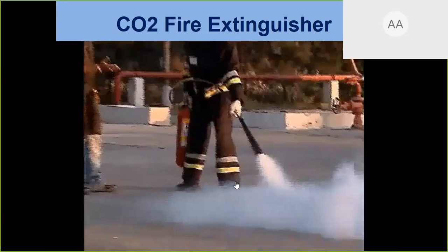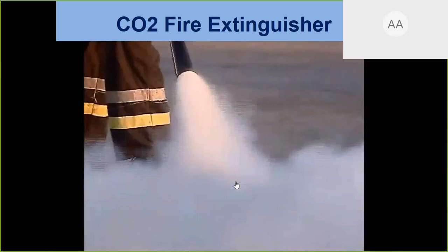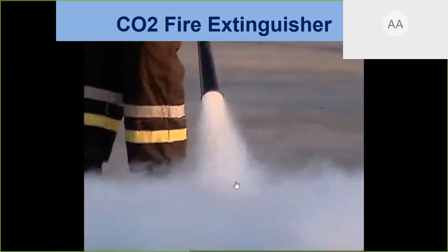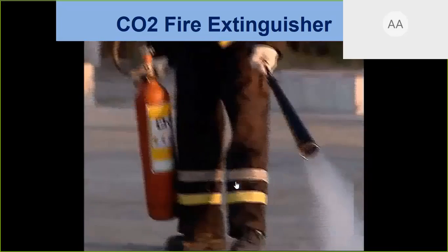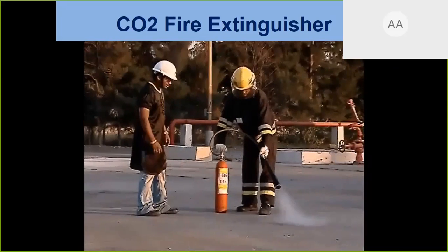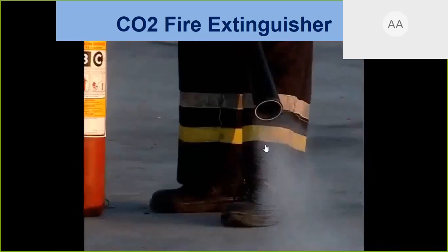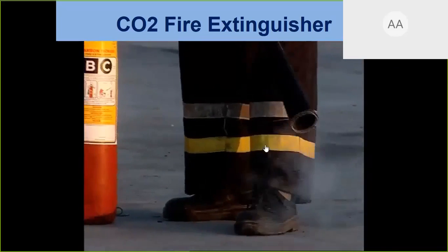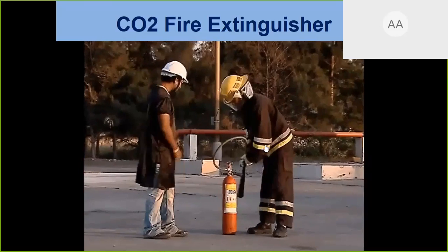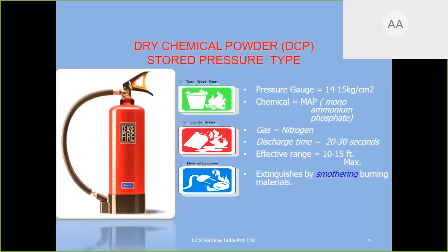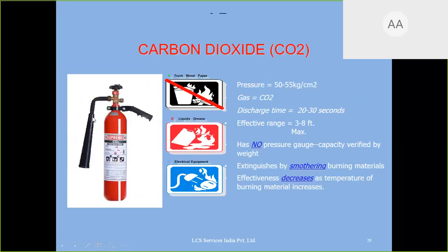So you see how the valve is opened. CO2 is coming out. Right? It is very, very highly pressurized and very cold in nature. So you have to hold it from the handle only. You cannot hold anywhere else. So my dear friends, you must notice that in DCP there is a pressure gauge, right? In CO2 no pressure gauge, and this hose is of the same diameter throughout, right? If I have to find out whether this extinguisher is CO2 or DCP, one is the hose diameter and the pressure gauge. In CO2, there is no pressure gauge and the diameter is increasing.